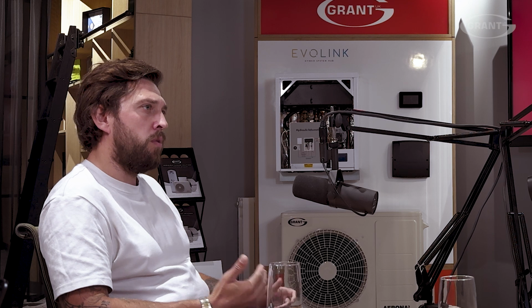But the thing with heat pumps is people are interested in the systems as well, so you can have that conversation with your customer. They can ring you and you can knock it up and down, you can change the curve. Generally I start lower than my design curve because you can knock it up. You'll generally find if people are already warm enough, they don't want to knock the curve down. They don't touch it. Whereas if you start off 4 or 5 degrees lower than what you're wanting, a lot of the time you don't have to move that up because your heat losses are slightly oversized, air changes, like you say, electrical equipment, solar gain. So you could just knock it up a little bit at a time and you'll find that sweet spot, and once you've found that, you won't have to change it again.